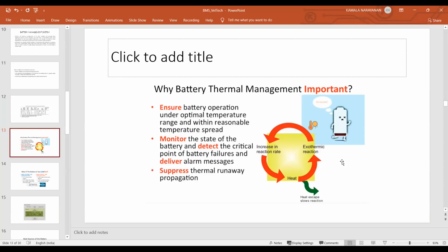And also to monitor the state of the battery, detect the critical point of battery failure, and deliver alarm messages whenever it is above or below the nominal value. For example, the voltage, current, or the temperature. Those are taken as the states. And to suppress thermal runaway propagation. Because if a particular cell has a thermal issue, it will propagate to all the cells, and ultimately the whole pack is going to get affected.